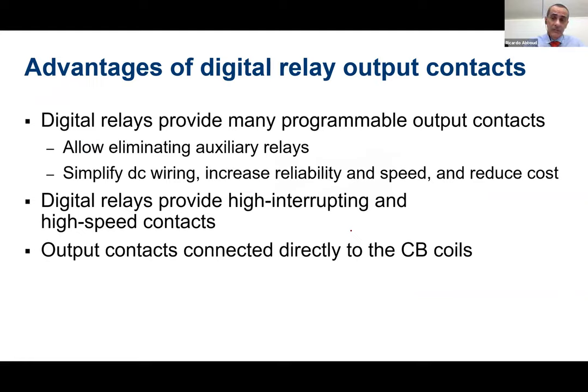In terms of output contacts, electromechanical relays have a very weak output contact. Okay. In the case of the digital relays, we can have high current interrupting contacts and high speed contacts. They can be really fast. How fast? 10 microseconds. I'm not talking about 10 milliseconds. I'm talking about 10 microseconds. It's almost instantaneous. And also they can interrupt large currents, 10 amps at 250 volts DC. So with that, we can act directly on the circuit breaker coils, the trip coils and close coils for the circuit breaker.